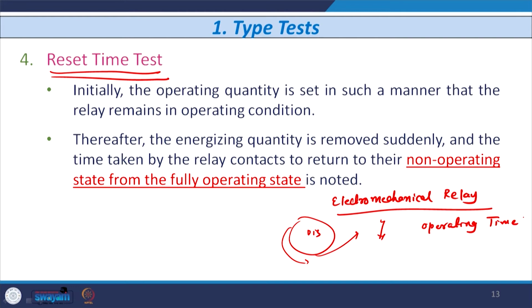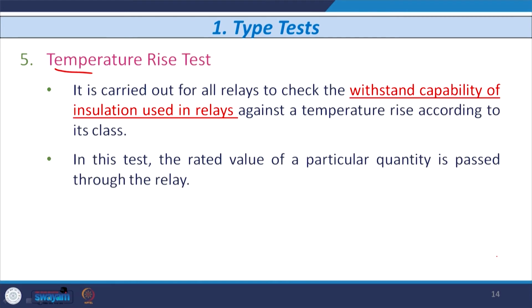Once the relay operates, the current becomes discontinued. So, again this disc will move from this position to its original value. The time required by the disc to come to the original position is known as the reset time, and there is a ratio known as resetting time divided by operating time. This ratio should be as high as possible.